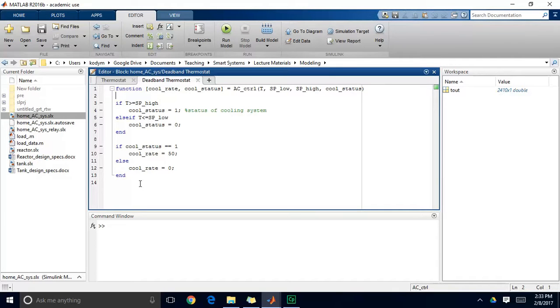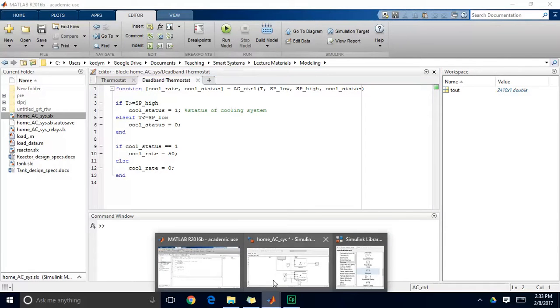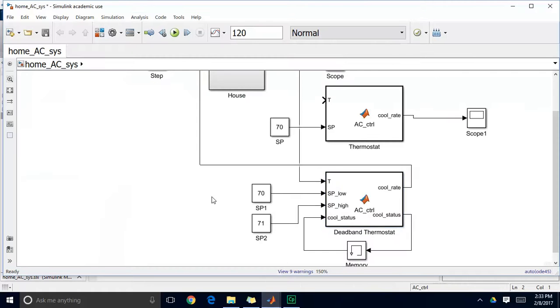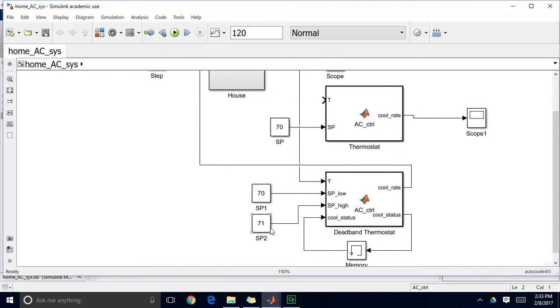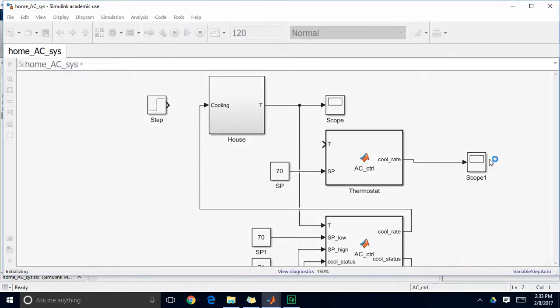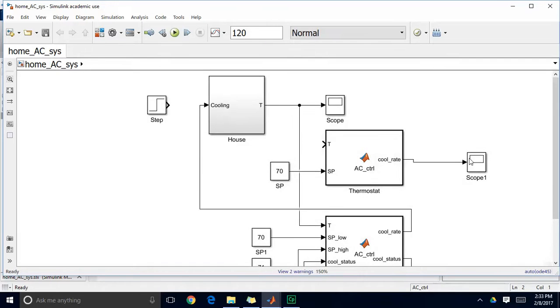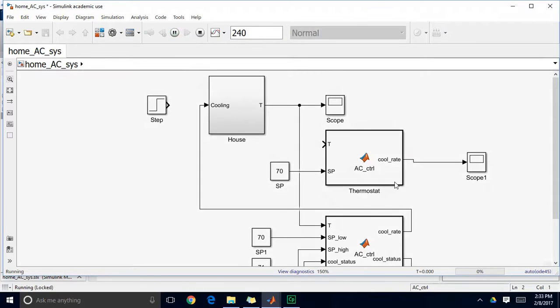So I'll show you how this works now by running this system. So I've got a low setpoint of 70 and a high setpoint of 71. And now I want to only turn on my system when it exceeds the high setpoint. And I don't want to turn it back off until it gets down below the low setpoint. So if I run it, I'm actually going to run it a little bit longer. So 240 minutes now. I'll look at my temperature.